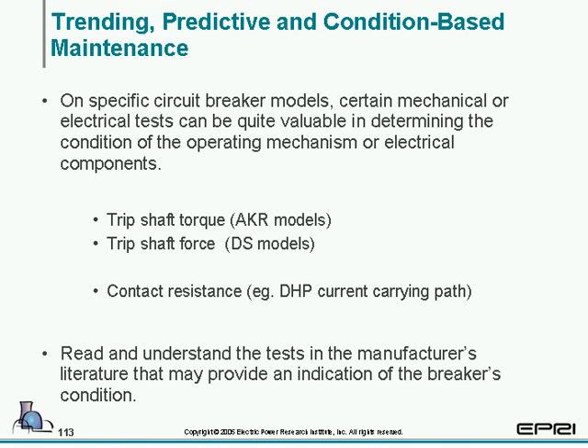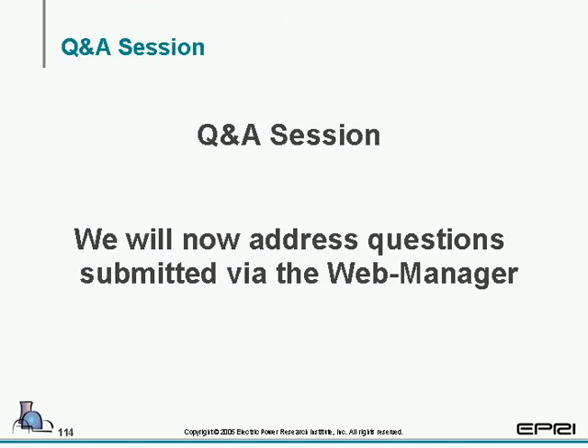And of course, contact resistance. For example, a Westinghouse DHP breaker has a bridge pivot inside the main current carrying components, and you can actually look at that contact resistance, and that will tell you a lot about how the breaker is put together and the condition of that bridge pivot. So the main thing is these are breaker specific, and to really have a good PM, you need to look at your maintenance manuals and understand what's in there and know what you can do on your breakers and how to maintain them.